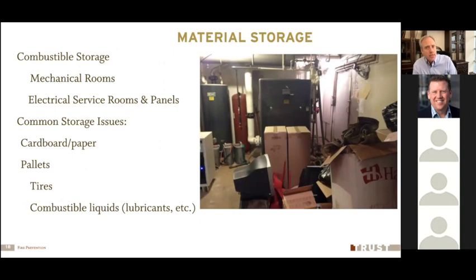Material storage is where we see a lot of challenges. Mechanical rooms and electrical service rooms, especially where we've got water heaters or furnaces or boilers, are all potential ignition sources for a fire. And we're all short on storage space, so it's really tempting to store a lot of materials in these mechanical rooms. And we need to make sure that we don't do that. If we do have any kind of combustible materials stored near electrical panels or heating equipment, we need to make sure we have at least a 3-foot space between that equipment and that combustible material. But an even better rule of thumb is just not to store any combustible materials in these rooms where we have these ignition sources. That's a real common problem we see.